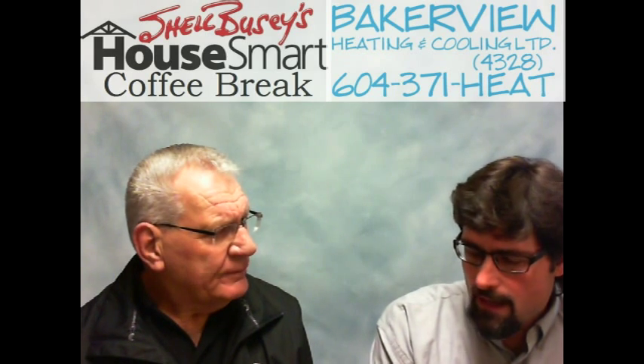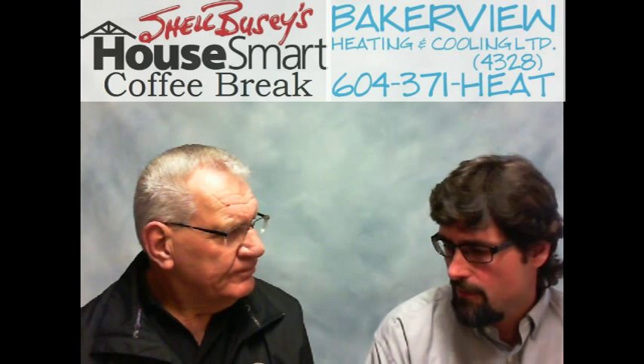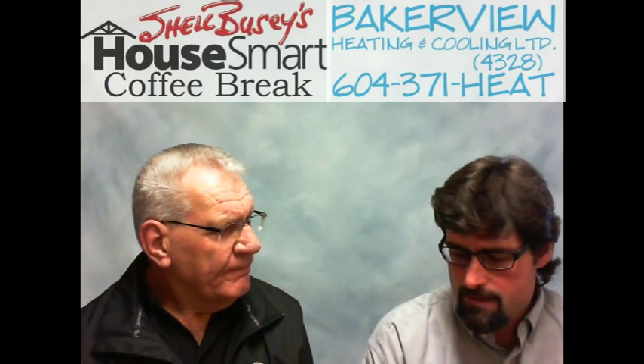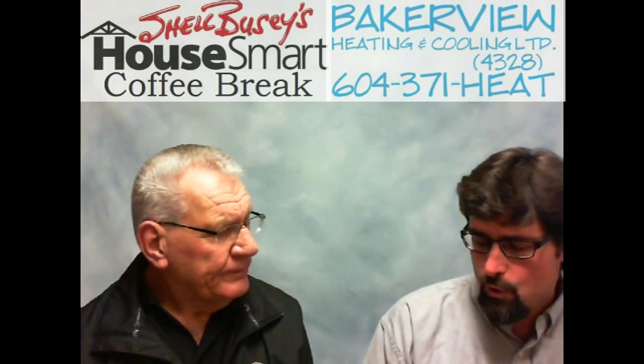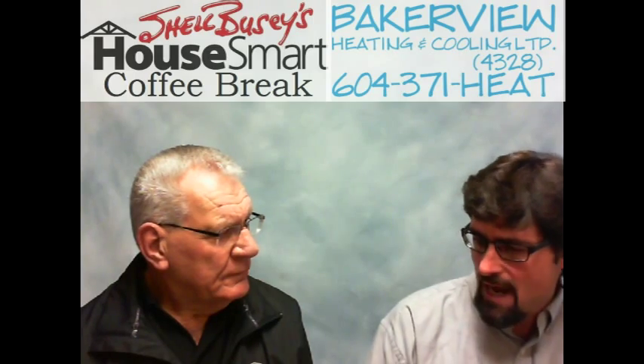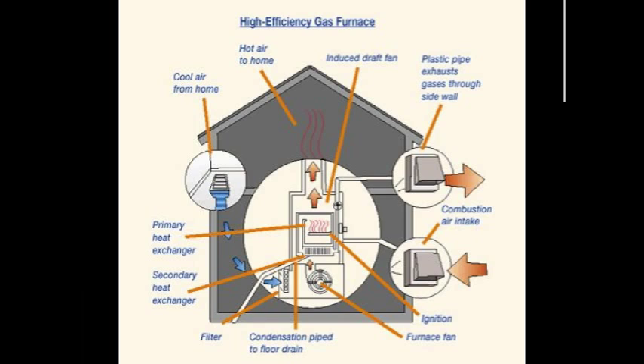Well, if you have a high-efficient furnace, one of the biggest things you need to make sure of is that your filter is clean. Another thing is, every high-efficient furnace condensates. So you want to make sure that condensate trap is clean because you don't want that furnace to back up with moisture. Also, a lot of houses don't have drains on the floor. So if you don't have a drain on the floor, you're going to have a condensate pump. They're a little bit loud, but that has to be cleaned out as well, and that'll prolong the life of that condensate pump.